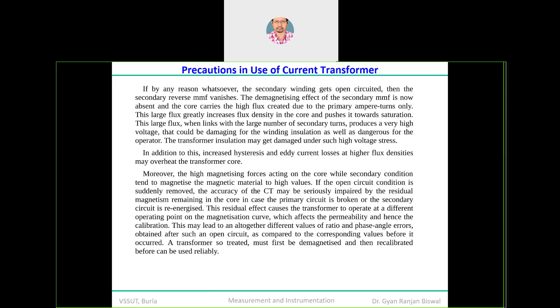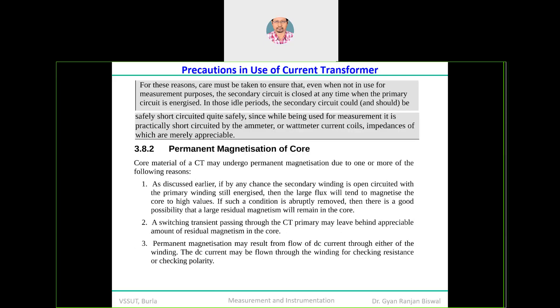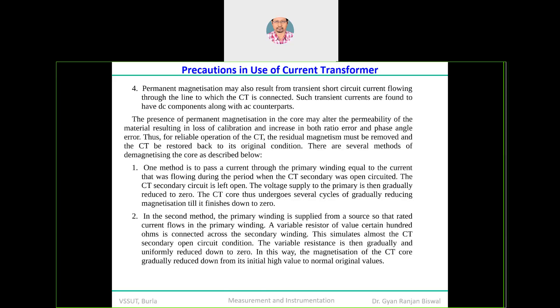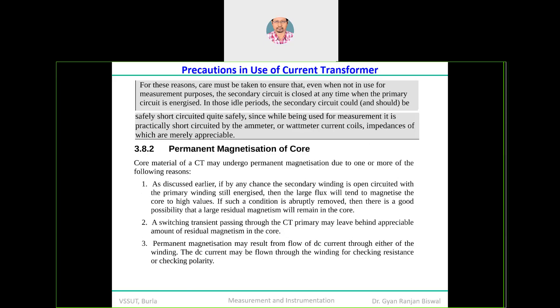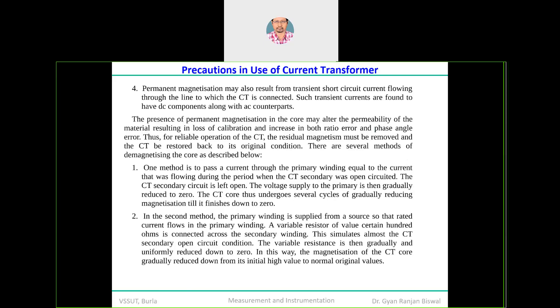If you keep the CT secondary open, there is no way to return the back EMF, which will increase the flux densities and cause overheating of the CT core. The core material of a current transformer may undergo permanent magnetization due to reasons already discussed. Please go through the last two or three slides carefully. With this, I am closing the recording of this lecture, and in the next lecture we will discuss further topics.